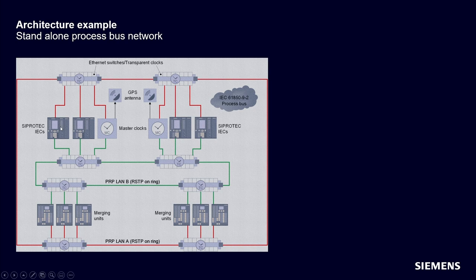So if you see, every device is connected to the red network, which is the PRP-B, and also to the green network, which is the PRP-B. So only the backbone switches are being connected with this RSTP ring. If you see, also the master clocks are double connected, or connected as redundant attached nodes, once to the red network and once to the green network as well.